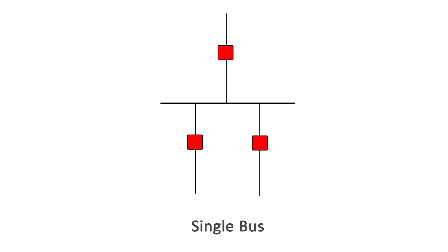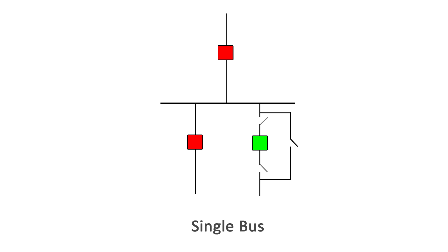Maintenance of any circuit breaker requires shutdown of the corresponding circuit line, and maintenance of the bus requires a complete shutdown of the bus. A bypass switch across the breaker should be used for maintenance of the corresponding breaker. Circuit protection is disabled in this case.